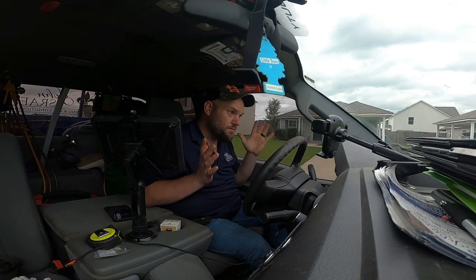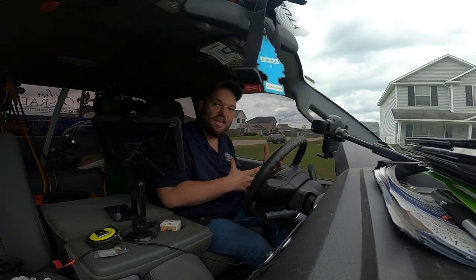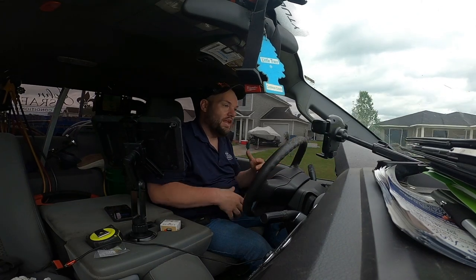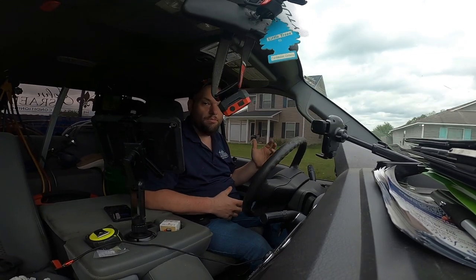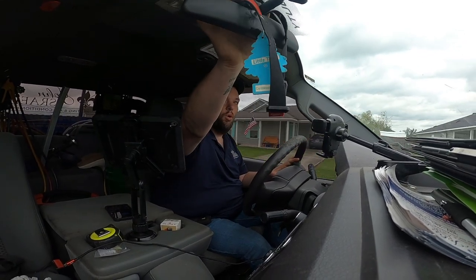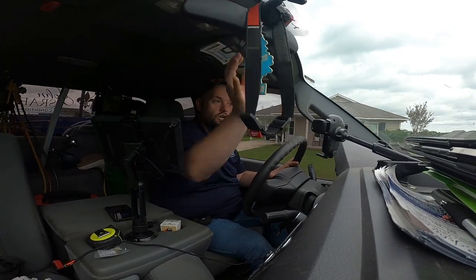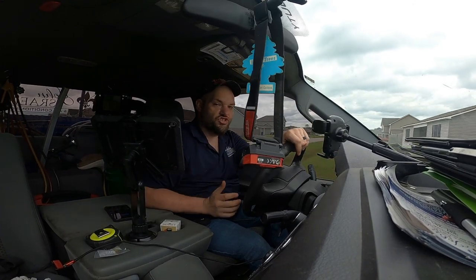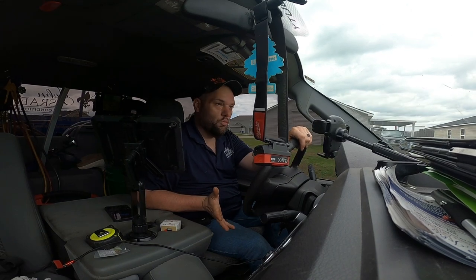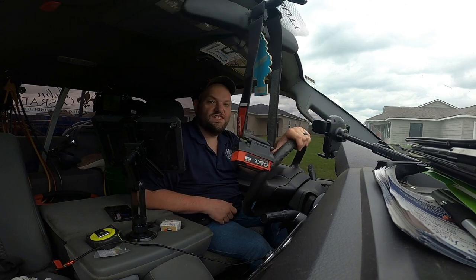I understand the concept and how it works. I think, you know, I mean, I do, but there's some things about it that I don't understand, and I'm not afraid to admit that. So I went back with the same model number board from Honeywell and hooked everything back up. I hooked that zone damper back up, and the system's working great. Both zones are working and cooling, so it is a successful repair.